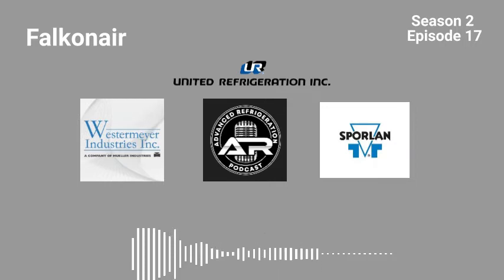I've seen an Emerson controller. Although they have all the pressure controls and everything, they still have a separate discharge temperature sensor on their discharge. And when I asked the question, why is that there? They said simply to get the warranty from the compressor manufacturer. So we have a partner who's a compressor manufacturer. Yeah. And because we are installing the sensors where we are installing them, he's actually extending the warranty, because it actually has an internal protection.